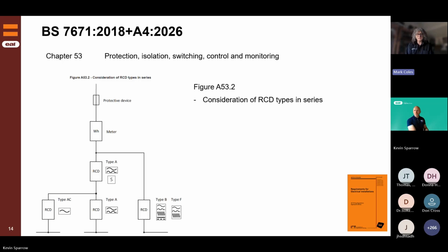The older types, like I was going to say like Kevin and me, but I'm older than him, so I'll say older types like me and Kevin, will remember that there used to be a Robin test instrument that allowed you to test RCDs. You pushed in the button and turned it like a thumb wheel, and you locked it. What that did was you could take a measurement of earth fault loop impedance, but conventionally the RCD would trip because you're directing the current elsewhere to earth. But I used to have one of those, Mark.